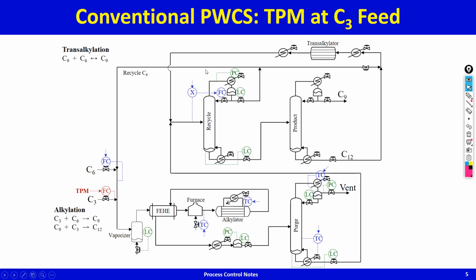You want exact fixing only for things related to product quality. Recycle streams, things can drift here and there, that's okay, as long as the drift is not too large, and the ratio, reflux in ratio with the feed, ensures that drift is not too large. Plus the feed to reflux ratio also gives some feed forward action, in the sense that if the feed is increasing, you increase the reflux, so top purity will be well regulated because of the feed forward action.